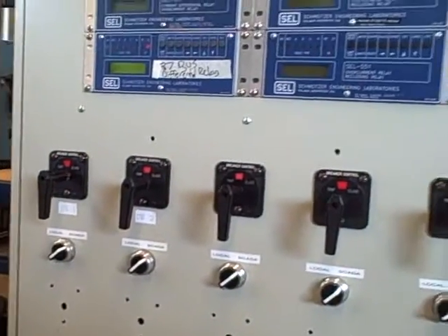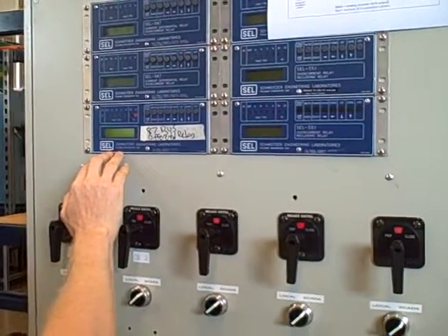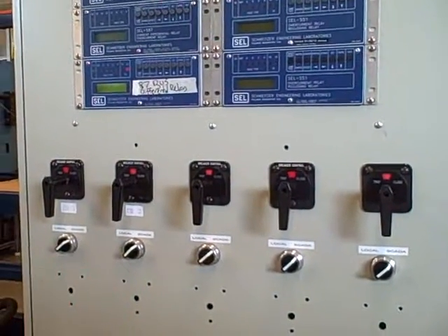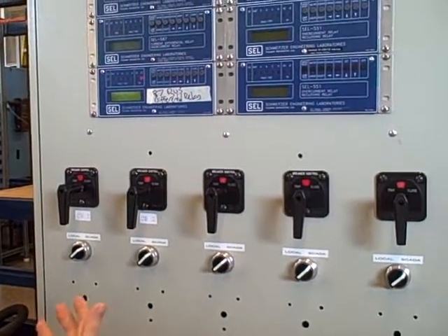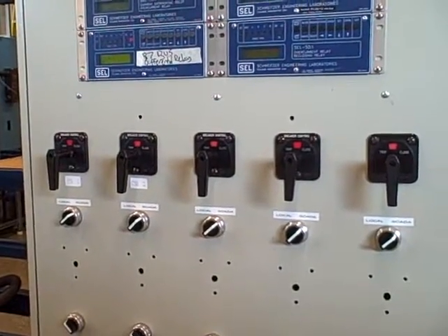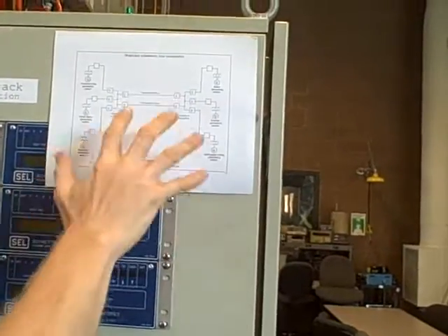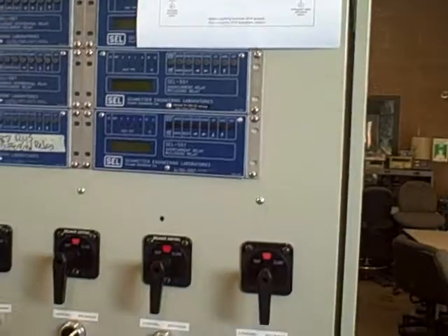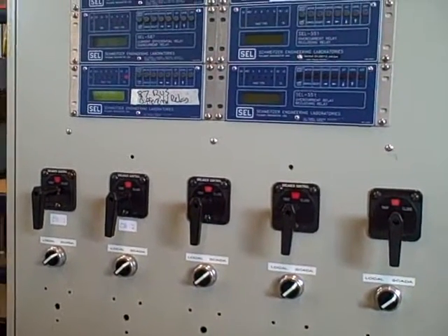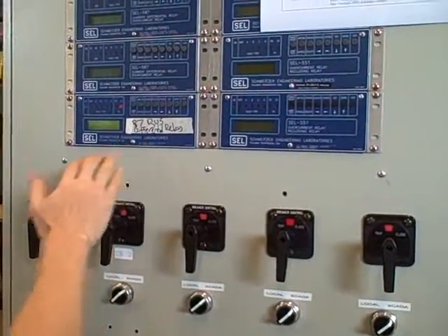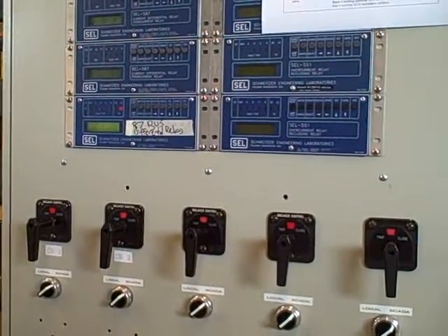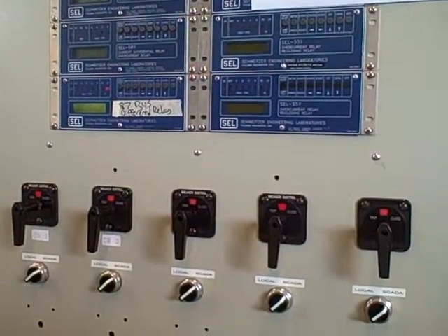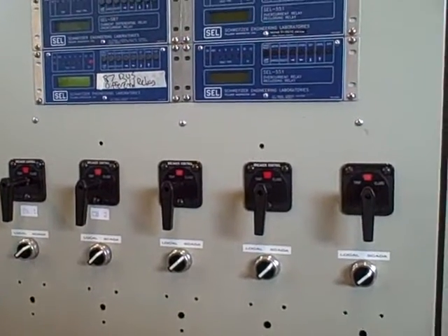That's a demonstration of how we can pulse the output on the Schweitzer protective relay system. You would not want to do this in a working system unless you really knew what you were doing, because you are forcing a trip event to occur. In this case none of our generators are online, everything's off, there's no power on the bus whatsoever, so we can trip and close breakers with impunity. But it's good to know about, especially if you are troubleshooting what you think is a faulted protective relay system — you may need to do a test like that to see what happens when the output contact closes. Keep in mind, if it's working like it should, it will trip whatever is designed to trip when you go ahead and do that.